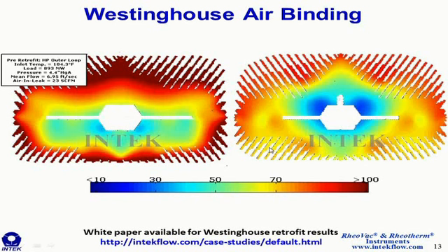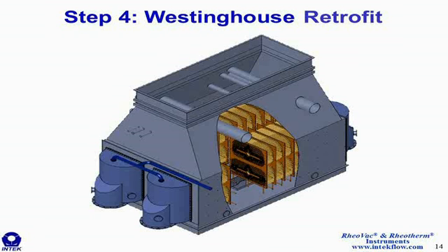There's a white paper available that discusses this retrofit on our website. I encourage you to go take a look at that white paper. But I'd like to show some of the results from a Westinghouse condenser that was retrofitted using this process. This is the condenser that was retrofitted. It's a single shell condenser. There are 4 of the Westinghouse starburst tube bundle patterns. Cooling water enters one side of the condenser, flows through the bundles, and exits out the other side. This is a 500 to 550 megawatt unit.